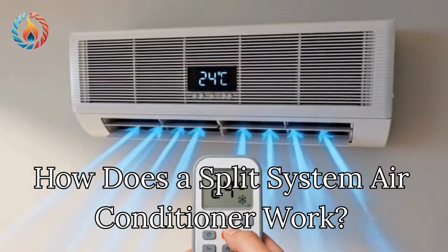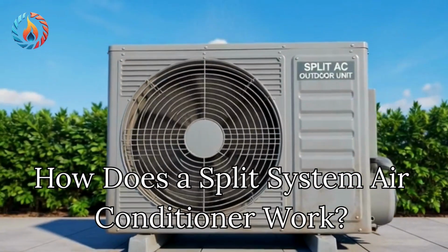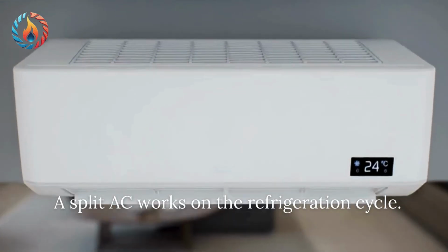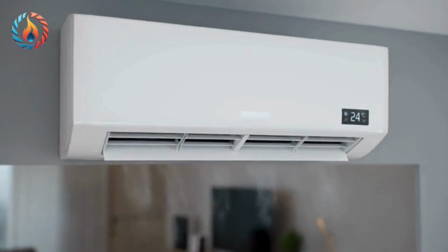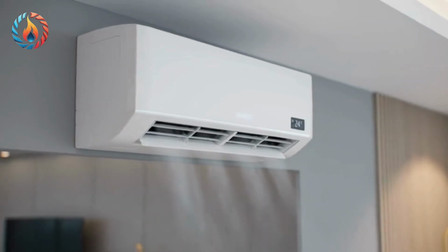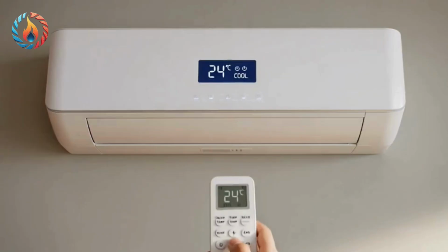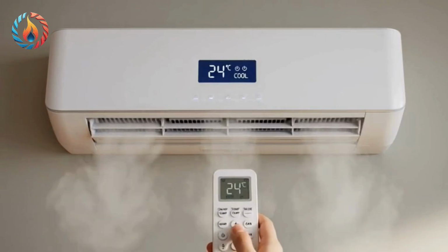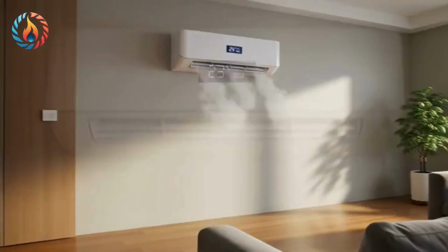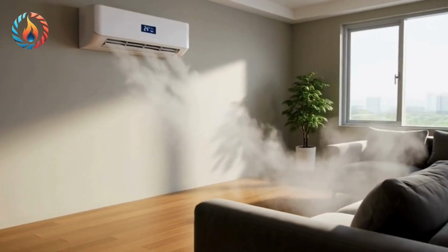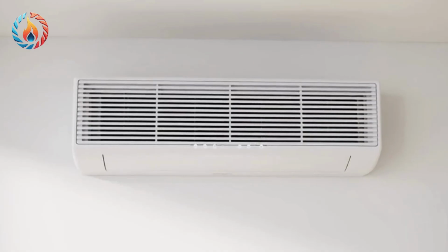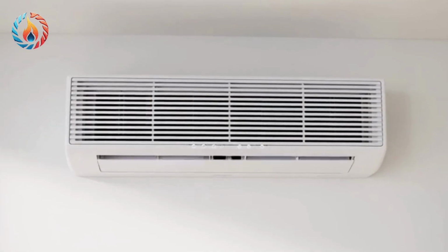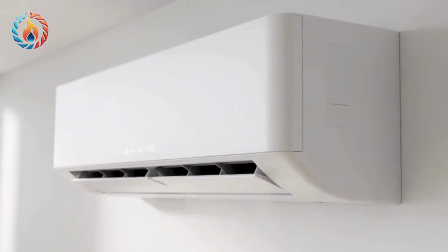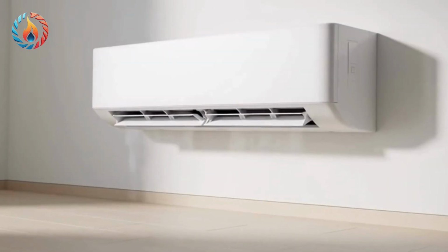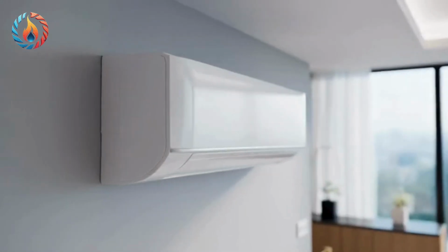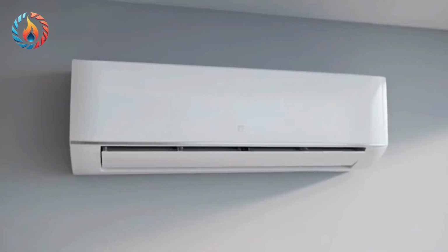How does a split-system air conditioner work? A split AC works on the refrigeration cycle. First, the refrigerant enters the compressor as a low-pressure gas. The compressor compresses it into a high-pressure, high-temperature gas. Next, this hot refrigerant flows through the condenser coil in the outdoor unit. The condenser fan blows outdoor air over the coil, releasing heat into the atmosphere. The refrigerant then becomes a high-pressure liquid.